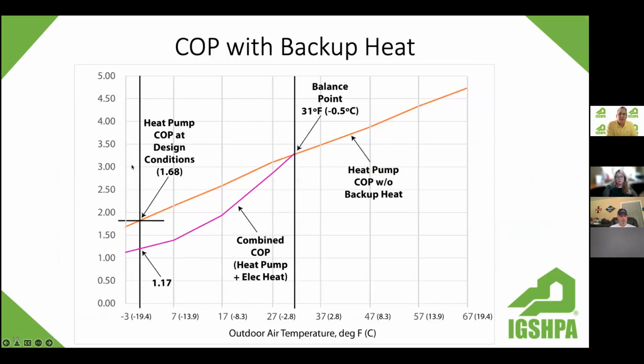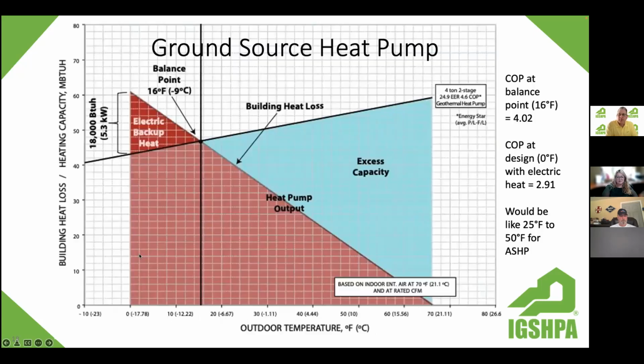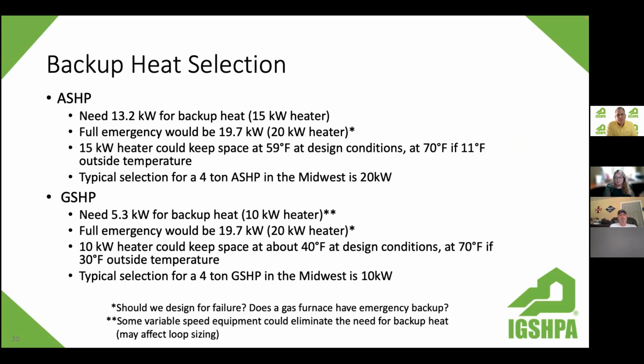That was versus 1.17. So you can see here where there is quite a bit of difference. It would be like running that air source heat pump between 25 degrees outside and 50 degrees outside. It would run really well at those conditions, and a lot of air source heat pumps do operate in that range. But as we get colder, that's where the electric heat need is significantly less. So how does that tie to the technical portion, the components that we're talking about? Well, it has a big influence here on our backup heat selection, assuming that we're going to go with a 2-stage unit versus variable speed, which could affect this, obviously.